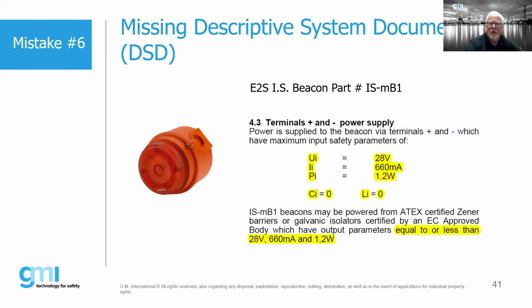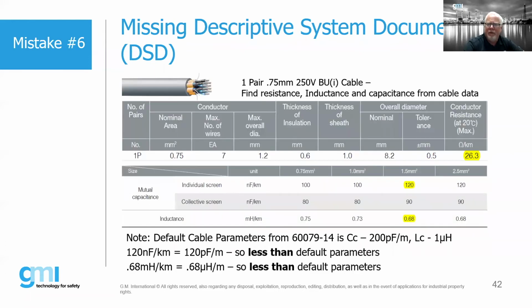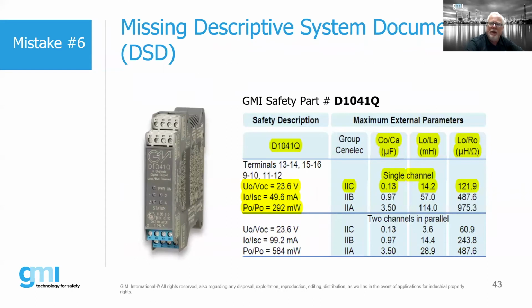And let me show you what we actually do when we put a DSD together. So here's an example where we get the parameters directly from, in this case, a beacon unit. So this gives us all the electrical parameters that we need to do our calculations. Then we take the information, in this case, the resistance of this cable, which we could go through in detail, but I won't do it since we only have a short amount of time. But basically, we need to find the resistance for the cable. Then we take the output information depending on the ignition curve for the output barrier, which is all published.